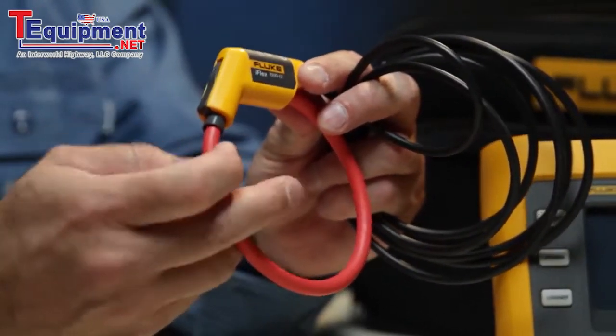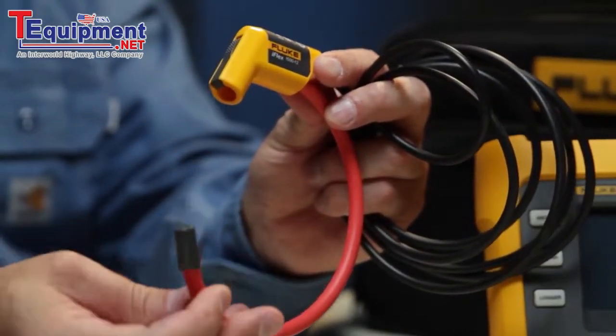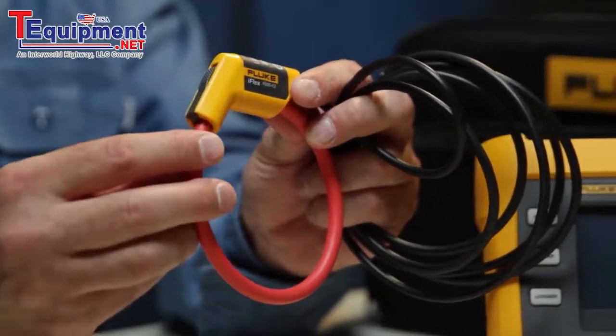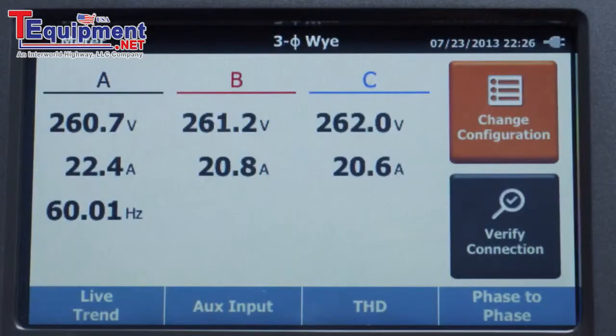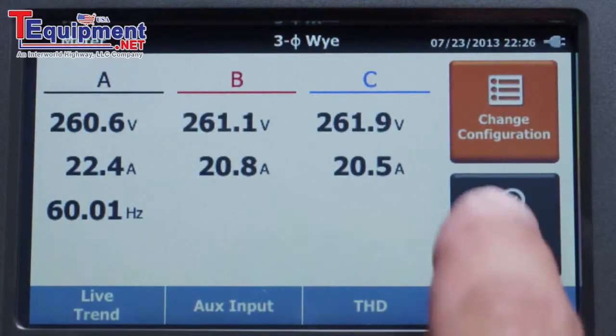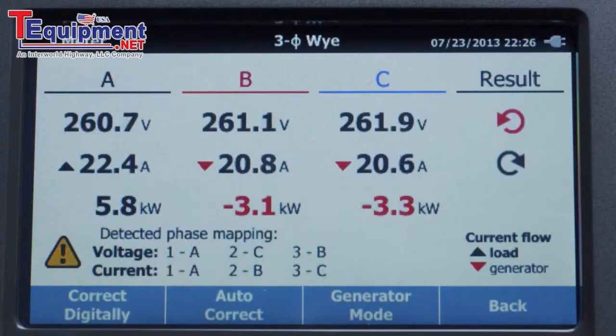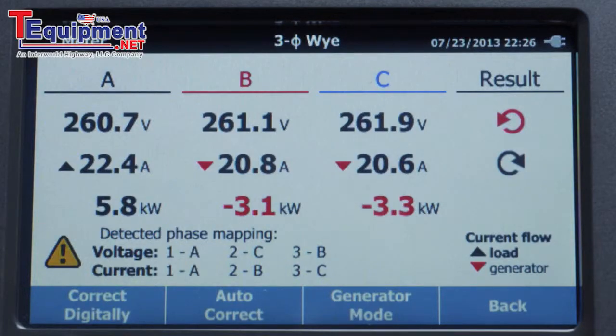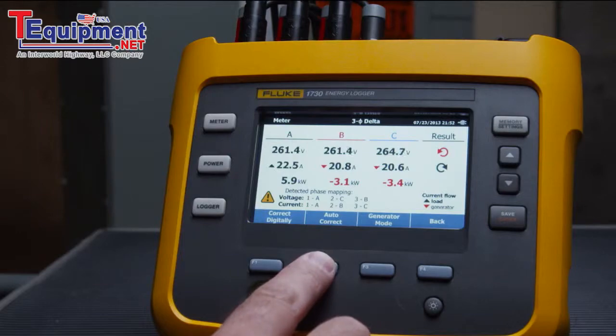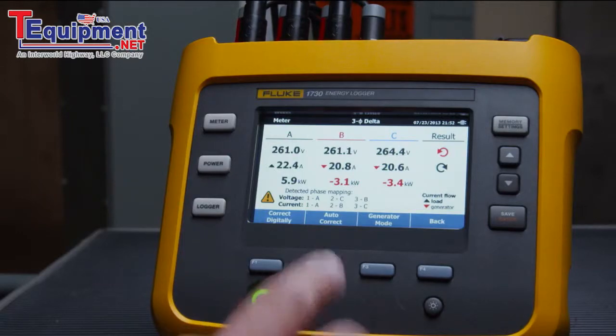Ensure the iFlex current probes match the selection compared to the voltage channels. Once the power is back online, press the Verify Connection button. The instrument will let you know if things are correct, or show where you may have made a mistake. If a mistake has been made, you can fix it on the instrument without having to disconnect anything, using the Autocorrect button.